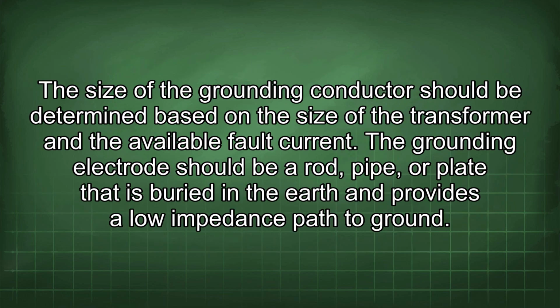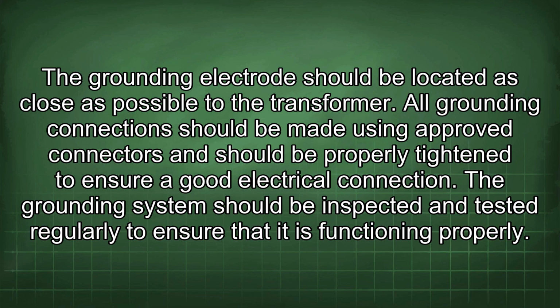The size of the grounding conductor should be determined based on the size of the transformer and the available fault current. The grounding electrode should be a rod, pipe, or plate that is buried in the earth and provides a low impedance path to ground. The grounding electrode should be located as close as possible to the transformer. All grounding connections should be made using approved connectors and should be properly tightened to ensure good electrical connection. The grounding system should be inspected and tested regularly to ensure that it is functioning properly.